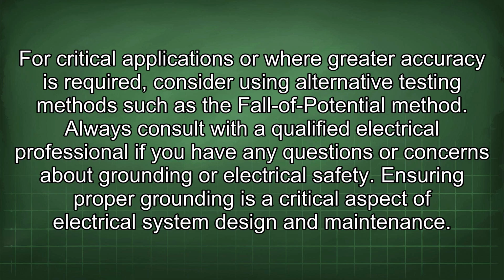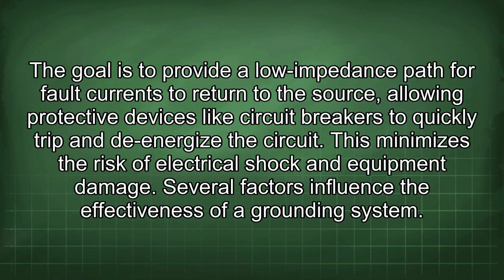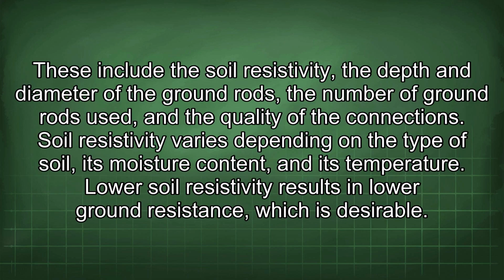Ensuring proper grounding is a critical aspect of electrical system design and maintenance. The goal is to provide a low-impedance path for fault currents to return to the source, allowing protective devices like circuit breakers to quickly trip and de-energize the circuit. This minimizes the risk of electrical shock and equipment damage. Several factors influence the effectiveness of a grounding system. These include the soil resistivity, the depth and diameter of the ground rods, the number of ground rods used, and the quality of the connections.